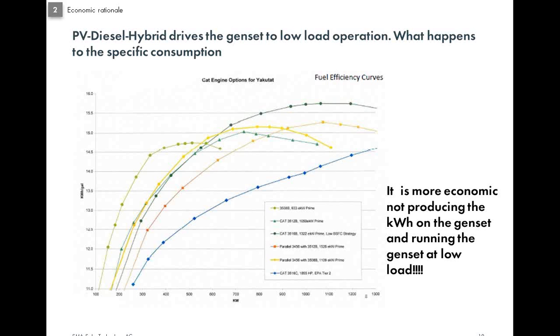So what we see is that there is a drop of 10 to 15% in the fuel efficiency of the generator when it goes from 100% utilization to say 30% utilization. And we do not expect that the DG set would go below 30% because our fuel save controller does not allow that, and the GCU itself would not allow that. So there is only a loss of 10 to 15% in generator efficiency.